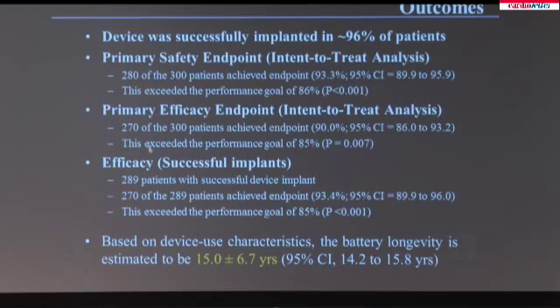There was also another efficacy analysis for those patients who had successful implants. That is, of the 300 patients in which the implant was attempted, 289 patients actually had a successful implant. Follow those patients out to 6 months, and it turns out 93.4% of those patients achieved adequate sensing and pacing thresholds. Also, based on the device use characteristics over these first 6 months, the battery longevity is estimated to be 15 years, the mean of 15 years, and you see the range between 14.2 and 15.8 years. At least that's a 95% confidence interval.